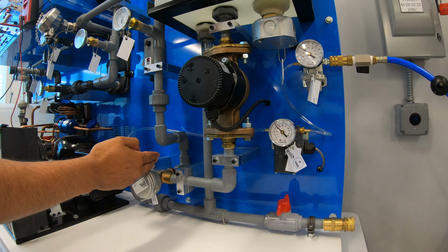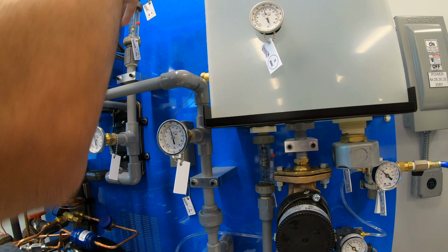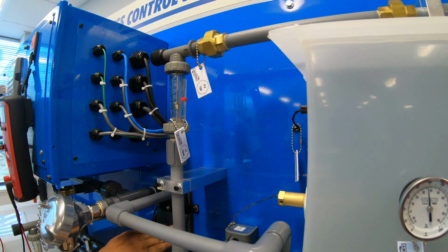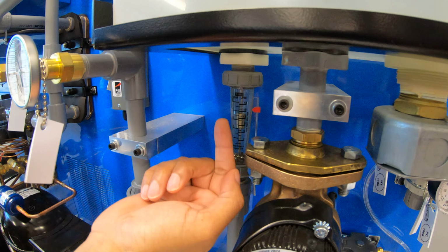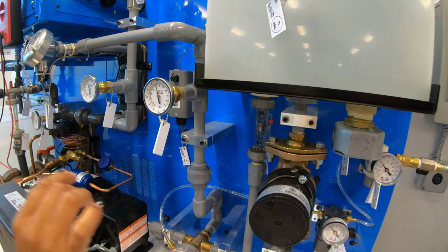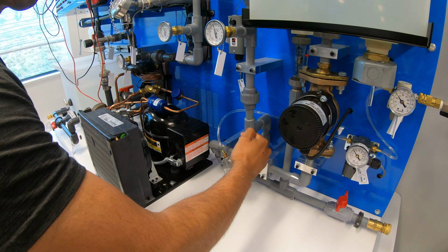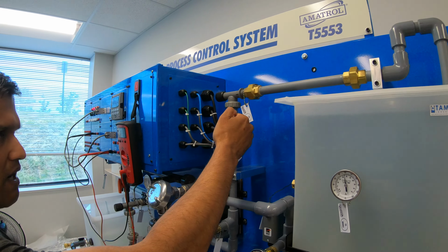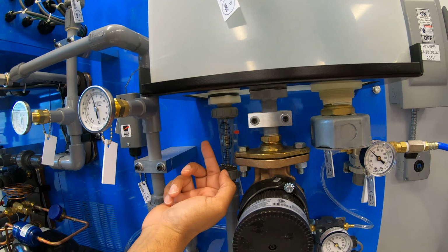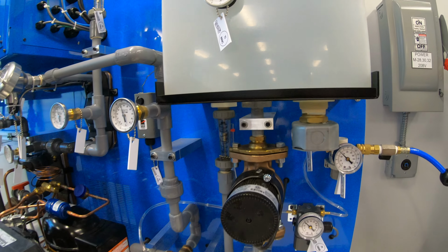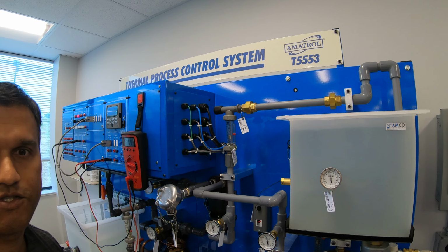So right now at 9, there's some water flowing, if you go through the pipe channels, flowing into the heat exchanger, okay? And there's some water flowing back into the bypass, right? If we increase the pressure using our PID, that means this three-way valve will close, closing the flow rate of the heat exchanger and increasing the flow rate of the bypass, okay? And then when we relieve the pressure, the flow rate of the bypass will go down and the flow rate of the heat exchanger will increase, right?